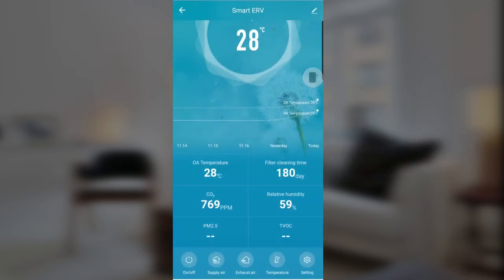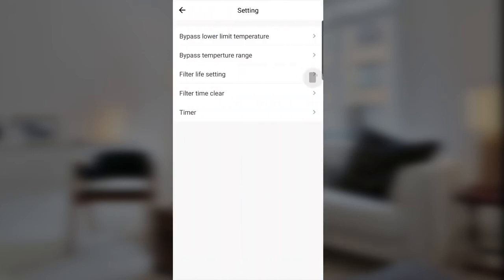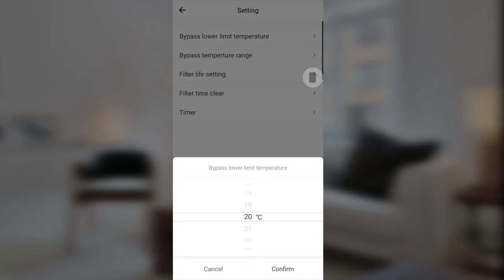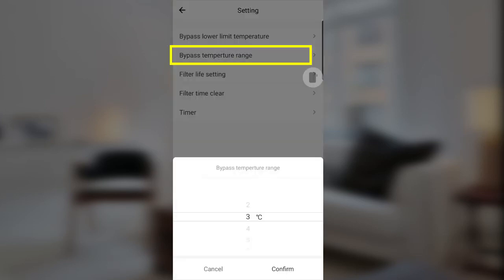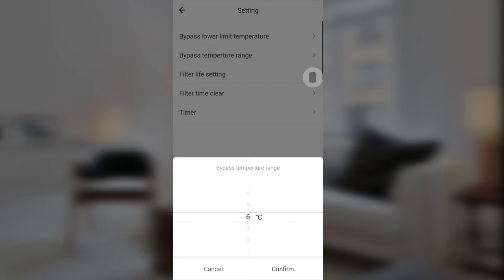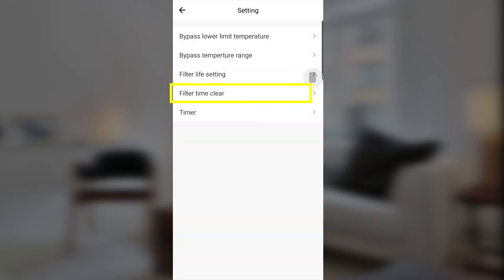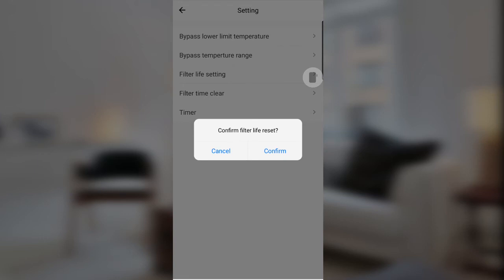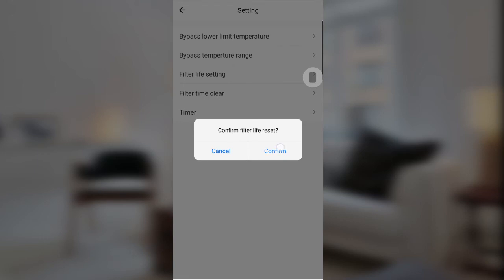Now let's go to Settings. You can set the bypass lower limit and bypass temperature range. There is also a filter life setting — 45 to 180 days. You have a filter timer and filter time reset, so you can clear the filter alarm.